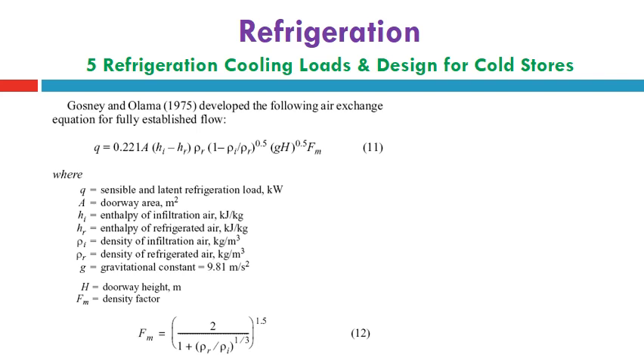In 1975 the following air exchange equation was developed, and it has been established and listed up to date in the ASHRAE Handbook of Refrigeration, chapter 12. In this equation number 11, Dr. Hani Ulama has listed this equation during his PhD in the UK. The equation gives Q equals 0.221 A, the doorway area, multiplied by delta H, HI minus HR.